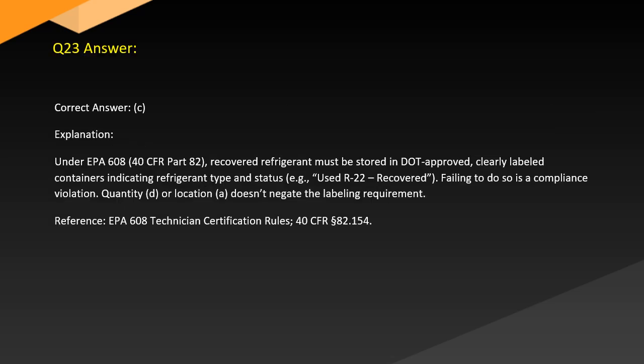Answer. Correct answer: C. Explanation. Under EPA 608, 40 CFR Part 82, recovered refrigerant must be stored in approved, clearly labeled containers indicating refrigerant type and status, e.g., used R22, recovered. Failing to do so is a compliance violation. Quantity (D) or location (A) doesn't negate the labeling requirement. Reference: EPA 608 Technician Certification Rules, 40 CFR Part 82.